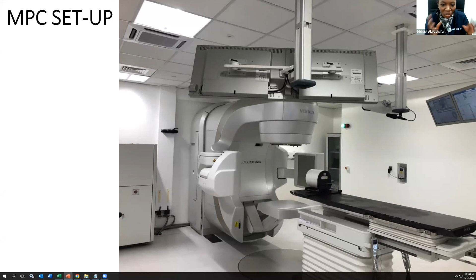So this is the setup of the MPC. We have what we call the MPC phantom, and it is positioned at a particular point on the couch, H2. The processes are all automated. And this is the check report for the MPC. Looking at it, everything is within threshold. For this MPC, your tolerance has to be within plus or minus 2%. Everything must be within plus or minus 2%. It checks automatically for you a lot of tests: the beam, collimation, reproducibility, and everything.